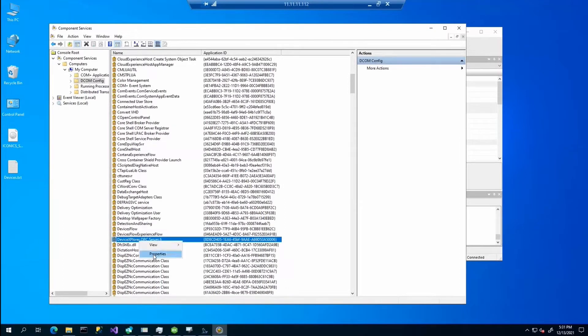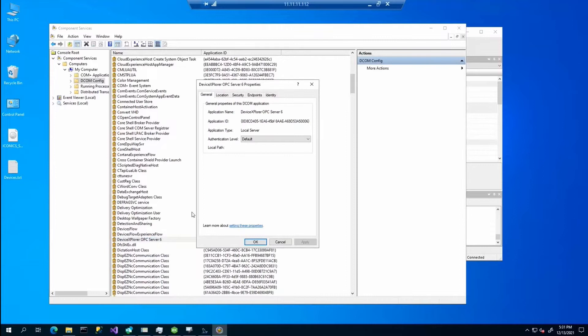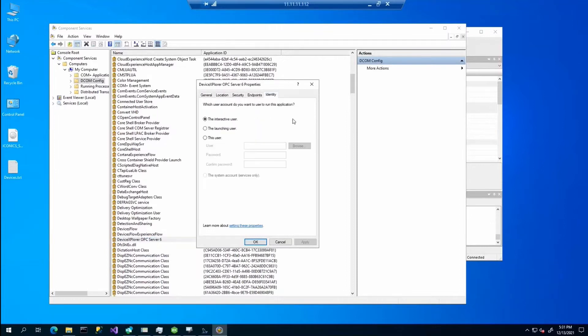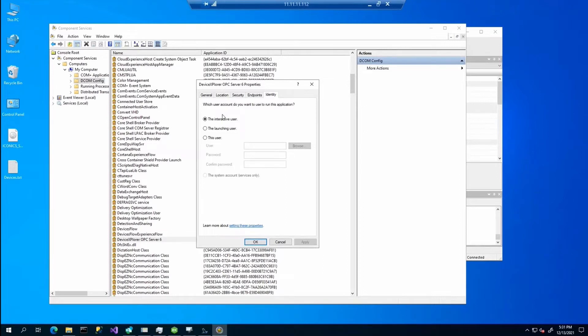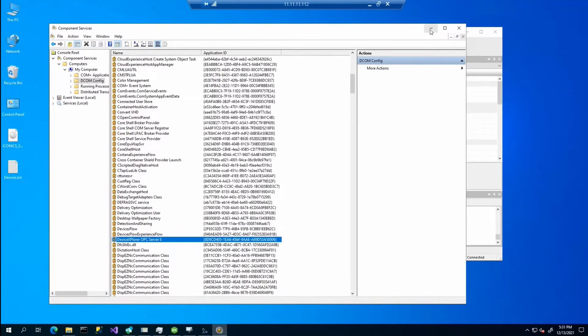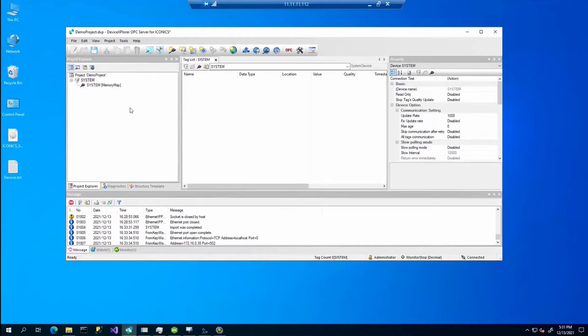You will find in DCOM config the device explorer OPC server 6. Right click on that, select properties and on the identity tab, you should select the interactive user. Once you will do this, you need to restart the server or the whole machine and it should work and you should be able to browse the server.